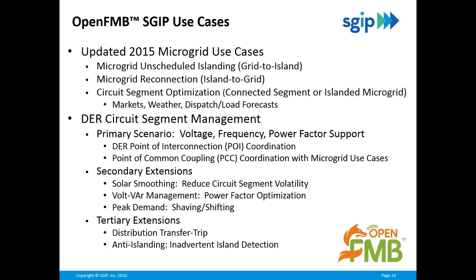And then there's another phenomenon that's very rare that we wanted to account for as another safety net, which we call inadvertent island detection. This covers cases where there could be deviations in frequency across your power system, and we want to make sure devices have the intelligence to coordinate so that if an islanding event occurred upstream, the systems that were out of balance would essentially protect themselves.